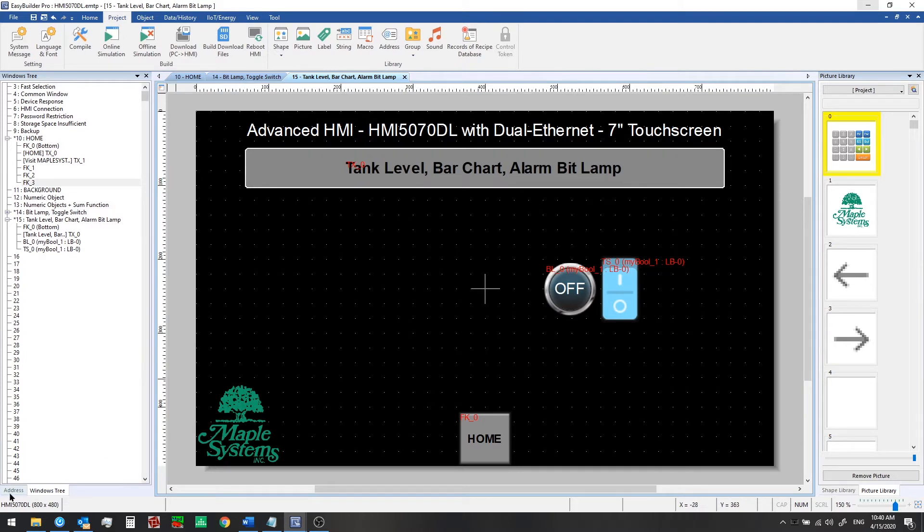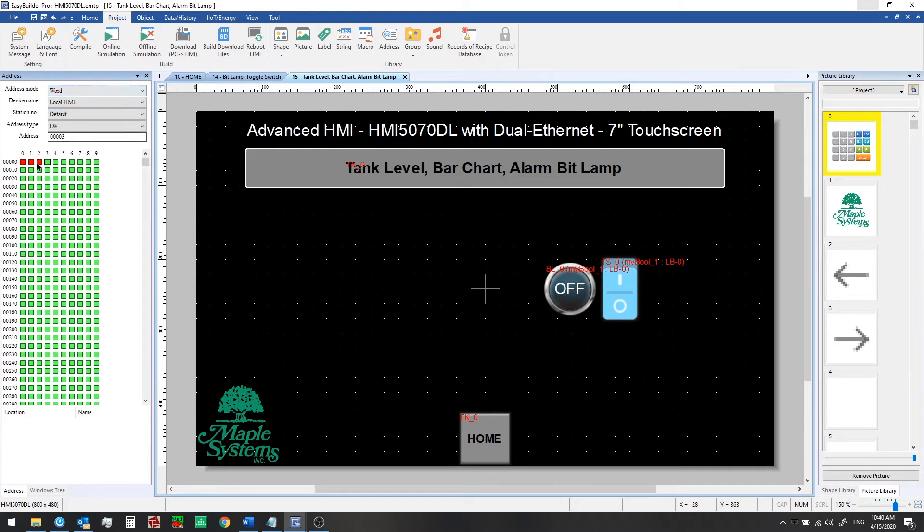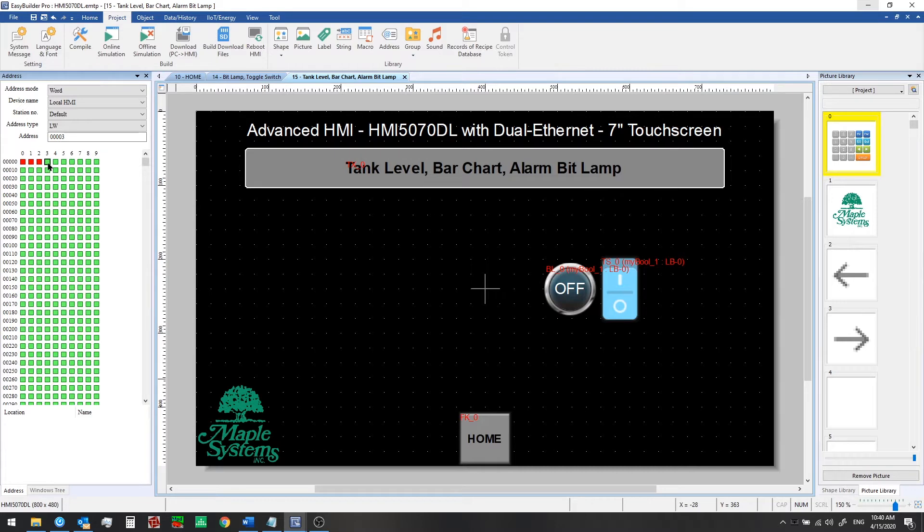But if you want a faster visual summary of this information, you can instead go to the address sidebar clicking down here and you can look at the word memory and the bit memory. So looking here we see that local word 0 through 2 are in use. That's denoted by the red squares and local word 3 is not in use. So this is our next available register which we'll use for our new tag we're going to create.